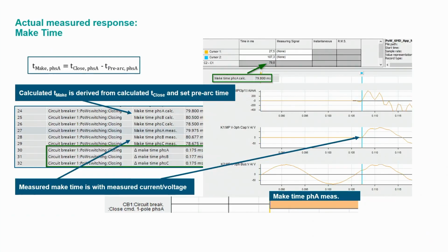The next values from the fault log that we check are the make time values. The first one is the calculated make time, for example, 79.8 milliseconds for phase A. This is calculated with the shown equation: calculated closing time minus set pre-arc time.